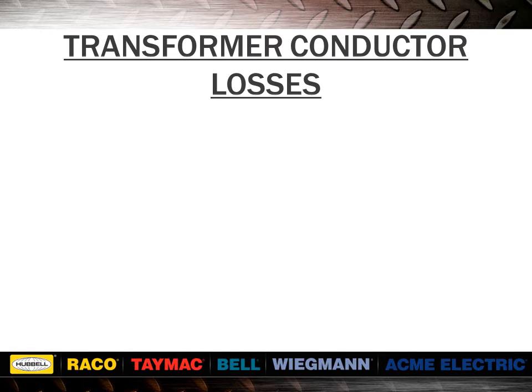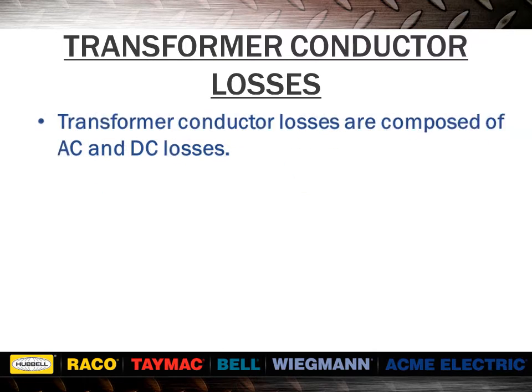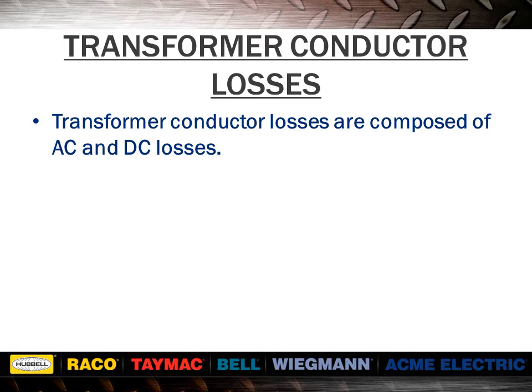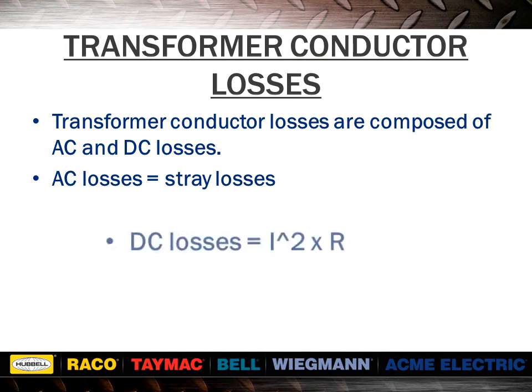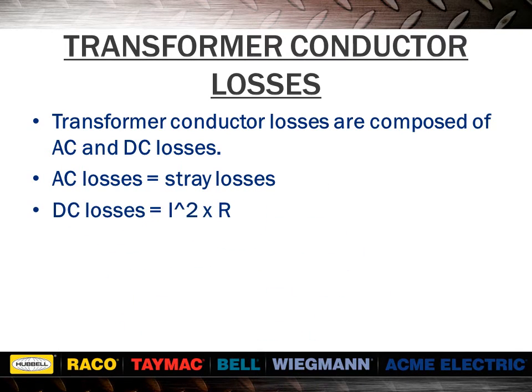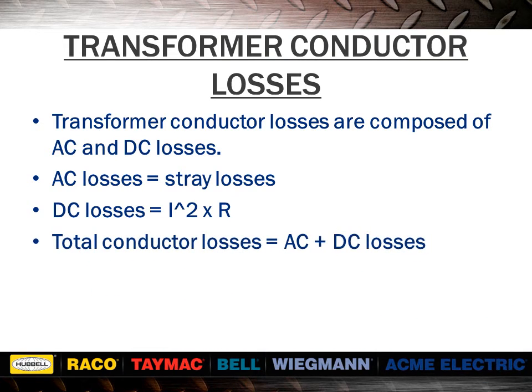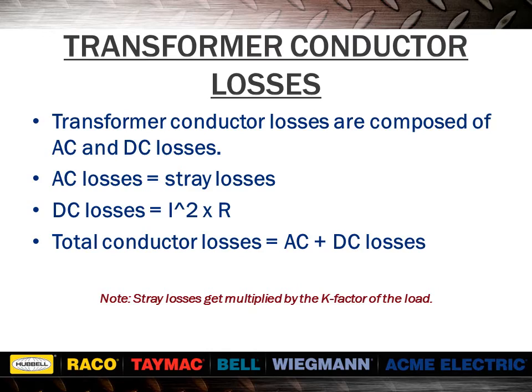Next, we will discuss transformer conductor losses. Transformer conductor losses are composed of AC and DC losses. AC losses equal stray losses; DC losses equal I²R. Total conductor losses equal AC plus DC losses. I²R losses can be easily determined from current and resistance, but stray losses are more difficult. Transformer total losses can be measured by putting a wattmeter in the primary supply circuit; the I²R losses can be subtracted from this total, and the remainder would be the stray losses.